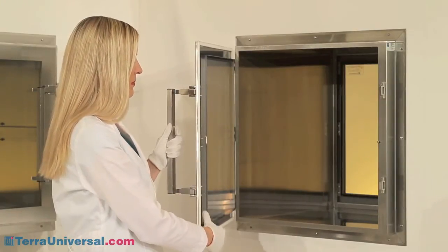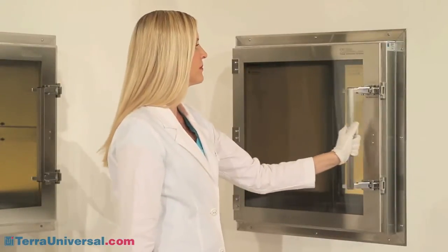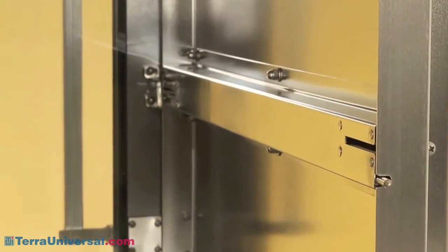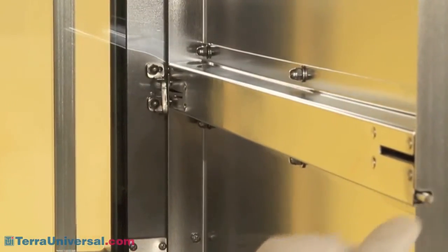The plastic doors themselves feature a double-wall design that enhances rigidity and strength for a better seal. The interlock mechanism, standard in all of these chambers, engages a catch that securely locks a door when the opposing side opens. Recent design improvements reduce the cracks and seams and include more robust locking pins rated for years of trouble-free operation.